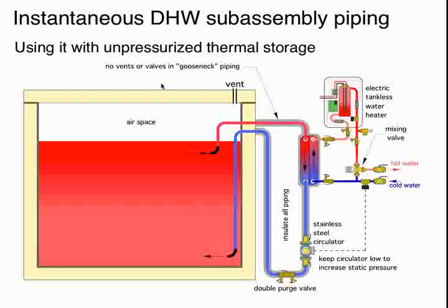Okay, we talked through this. The operating cost of that circulator, less than $1 per year. Here's how you could set it up for an open tank. If you were using a large unpressurized tank, we could use what's called gooseneck piping through the sidewall above the water line. Basically the same detail. You would want to use either a bronze or a stainless steel circulator here because this is an open system. And you want to keep the circulator low so you have some static head on it.